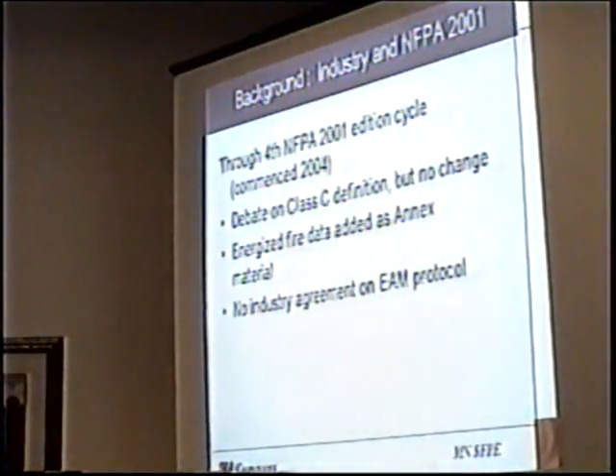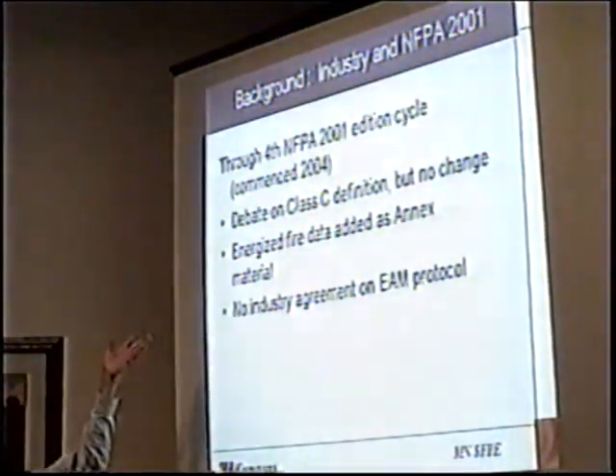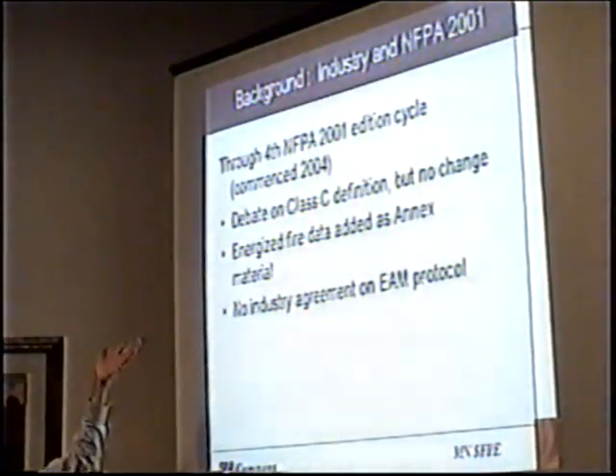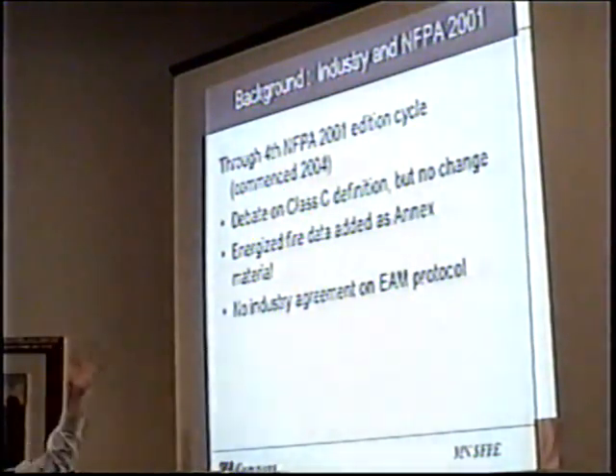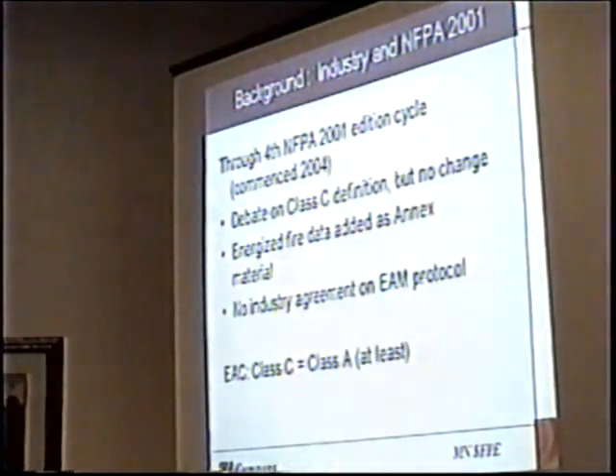We do have energized fire data that's been developed over the course of the last 8 years. A number of people have done a lot of work on that. In fact, we'll show you some examples here in a second. But basically, it's a conglomeration of different people's ideas of what energy augmented combustion should be. Nothing standard, nothing worked on in a concerted effort as an industry. So there's no agreement on what an energy augmented combustion protocol would be. And so an EAC, Class C equals Class A, at least. That's the definition of it right now. It's the best we can do. What you do for a Class A is what you should do for Class C, at least.